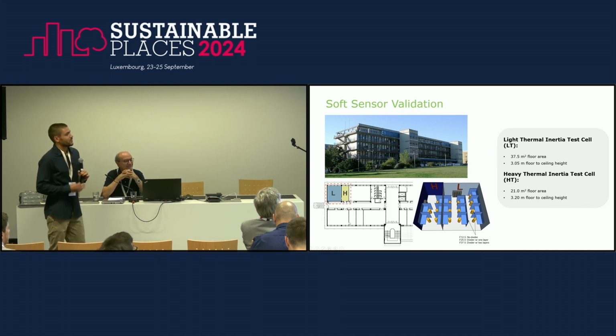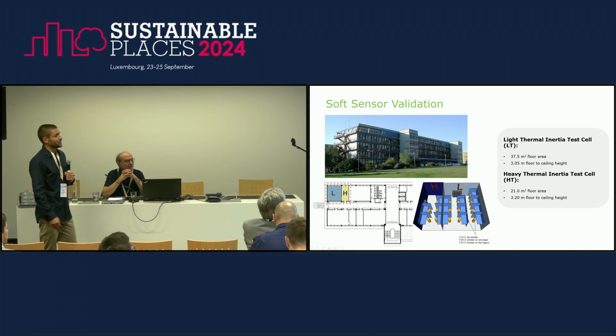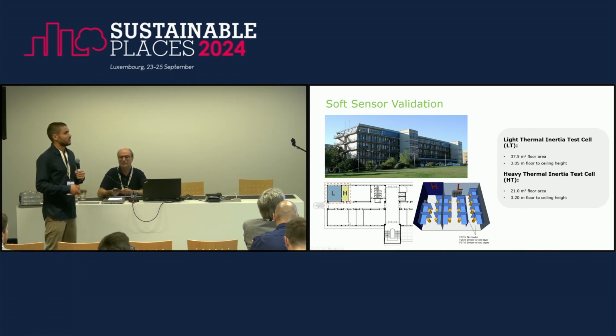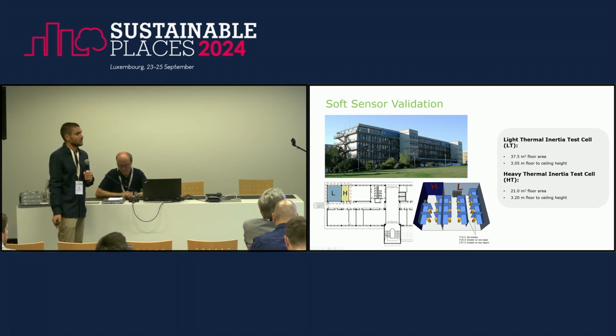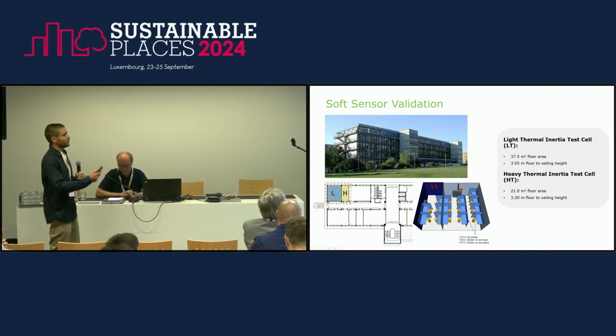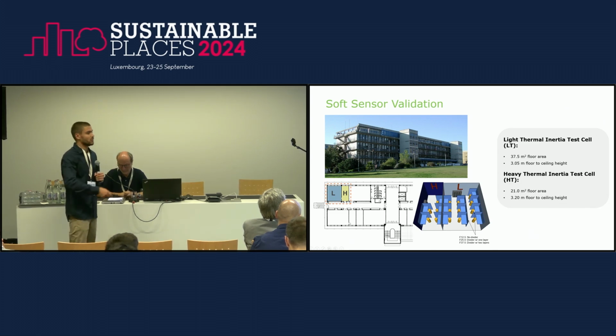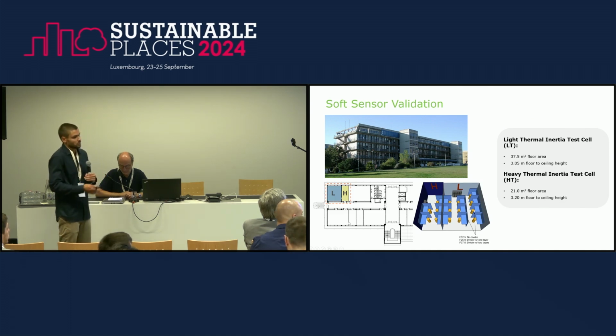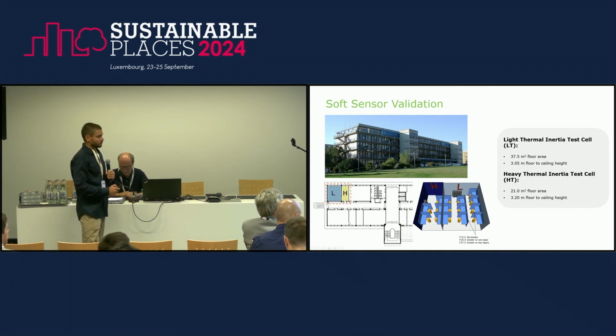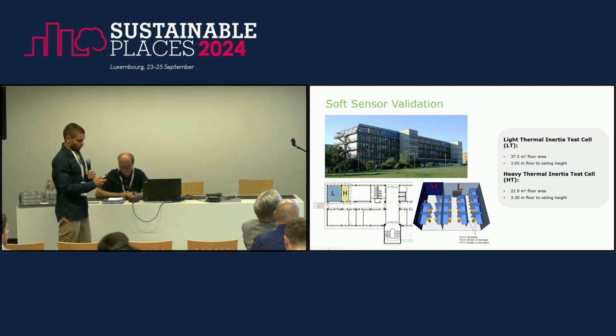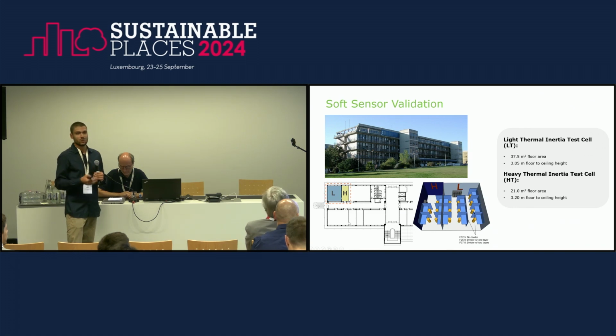After we developed the concept, we started by validating our soft sensor in 2 different test cells that we have. These test cells were really good to test whether our soft sensor can capture different thermal inertia within zones. We have 2 test cells, one with very light inertia with a lot of insulation inside, and the other one very heavy, mostly concrete. What we conclude is that the model can capture different capacitance within the zones.